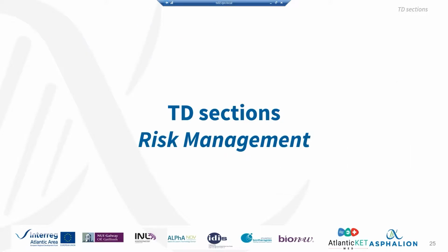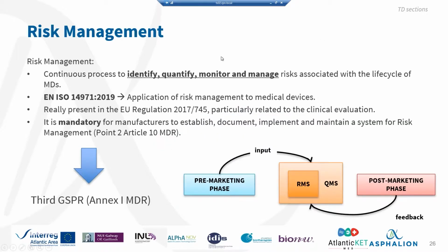So once we have finished with the general safety and performance requirements, let's talk about the risk management of your device. Risk management is a task that is mandatory for all devices that have to comply with the medical devices regulation.